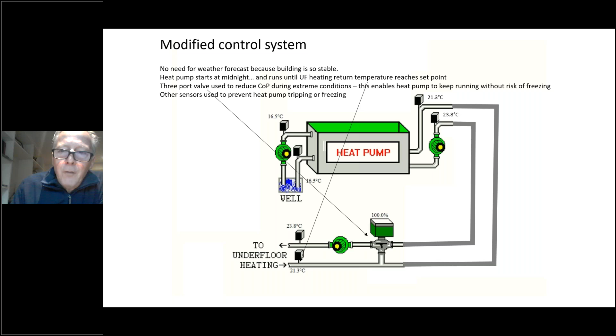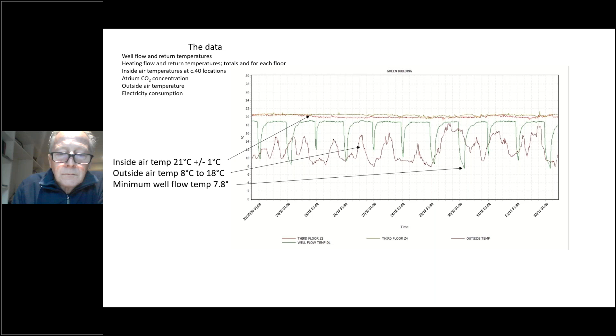And we've been collecting data from then to now, and here are some examples. I collect the well flow and return temperatures, the heating flow and return temperatures for the entire building and for each floor, the inside air temperature at approximately 40 locations, the CO2 concentrations in the building, the outside air temperature, and electricity consumption. And that's a plot that I downloaded relatively recently. And it shows that we're maintaining inside air temperature at 21 degrees C plus or minus 1, which is a target. You can see the outside air temperature during that period varied from 8 degrees to 18 degrees. Typical winter weather, a bit warmer than it was 20 years ago. And the minimal well flow temperature is 7.8 degrees.